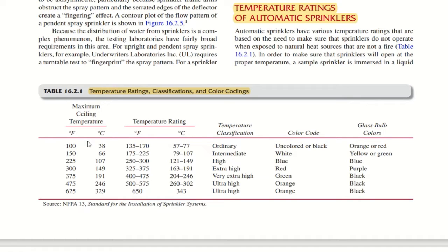However, here just to go through in a quicker way, you can see maximum ceiling temperature in degree Fahrenheit and degree Celsius, and the temperature rating of the sprinklers in degree Fahrenheit and degree Celsius. Here you have temperature classification. The sprinklers are classified based on the temperature rating as ordinary, intermediate, high, extra high, very extra high, ultra high, and the color code of the sprinkler itself, not the bulbs: uncolored or black, white, blue, red, green, orange. We will see these things in later stages. So glass bulb colors, when we look at the glass bulb we can also identify whether the classification is ordinary or intermediate. Glass bulb colors: orange or red, yellow or green, blue, purple, black.